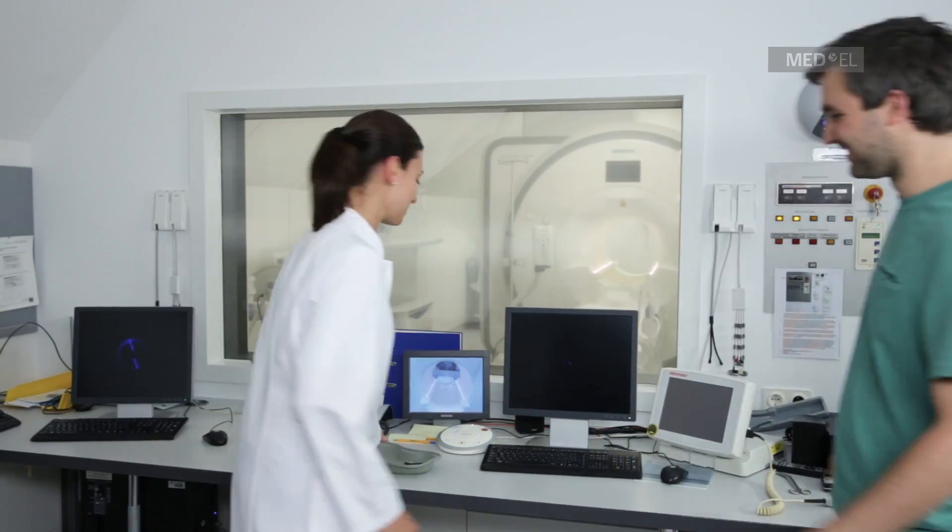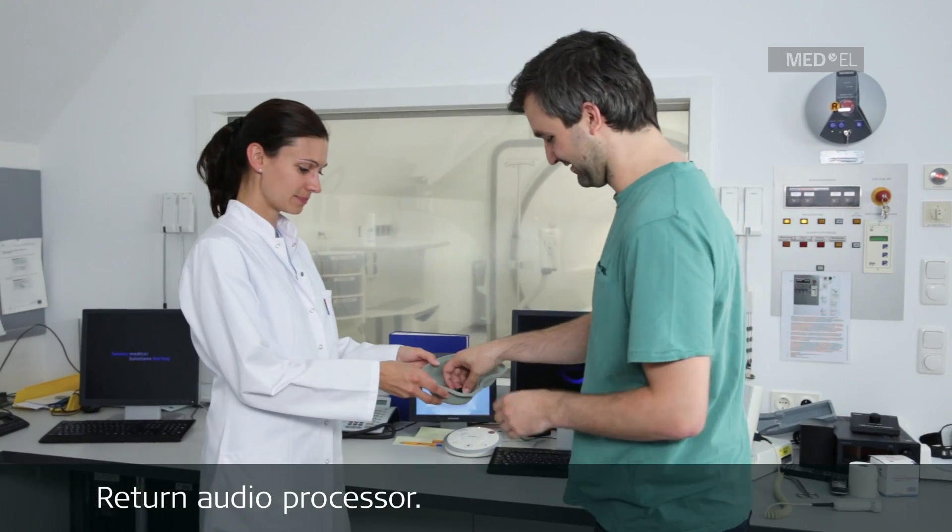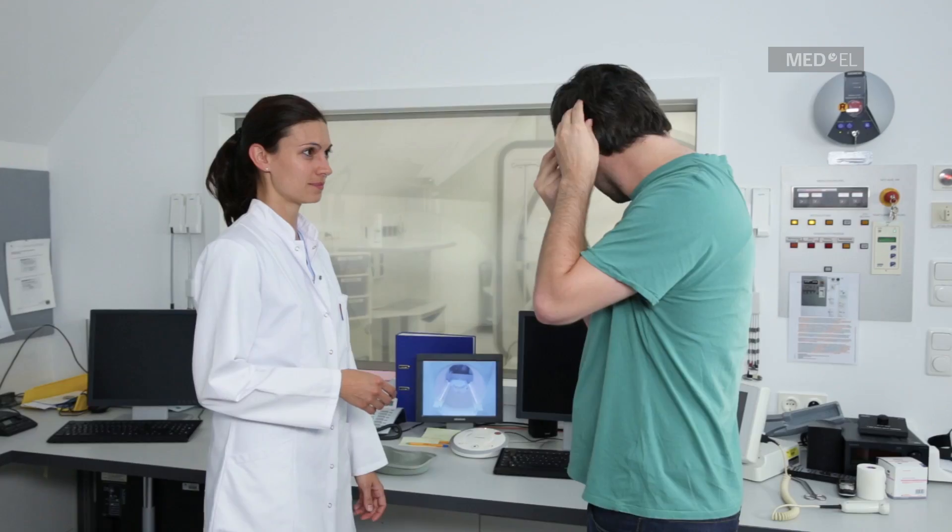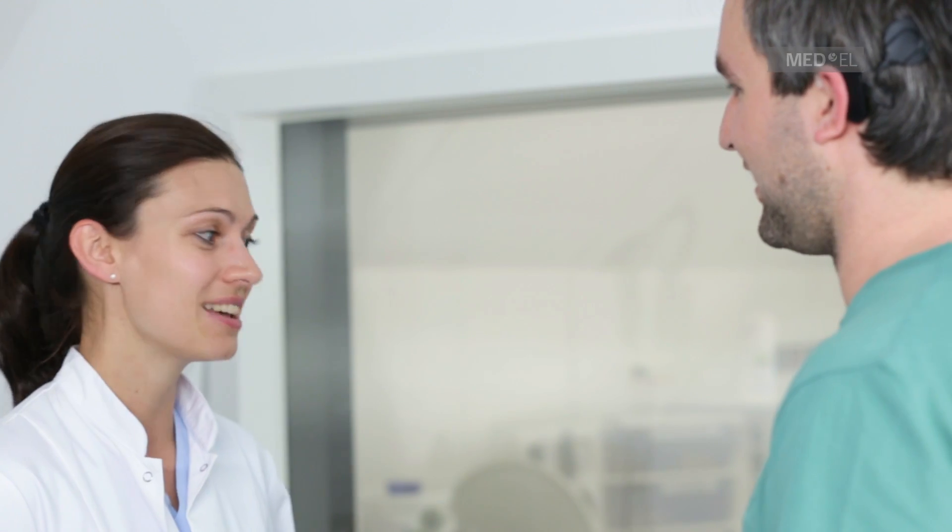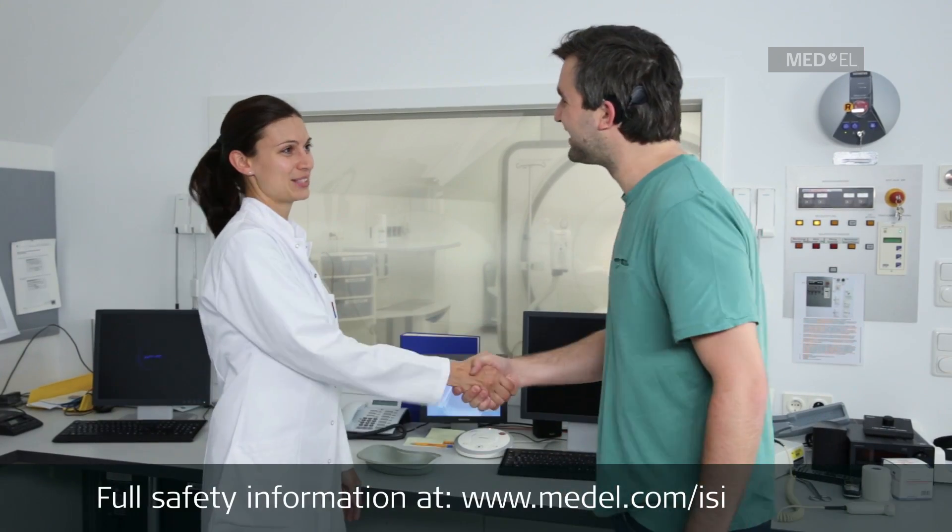Once the scan is complete, the patient can return to using their audio processor after leaving the scanner room. By following these basic conditions, you can safely MRI scan patients with a synchrony implant. Please contact your local MED-EL representative if you have further questions.